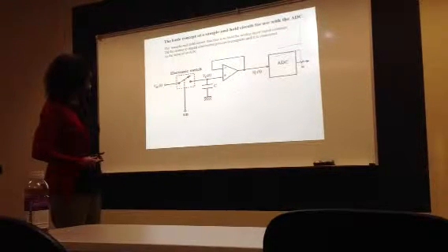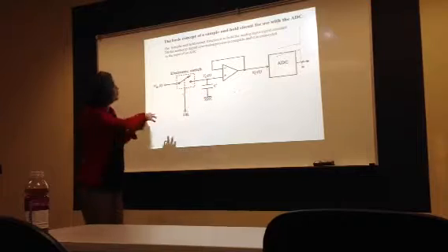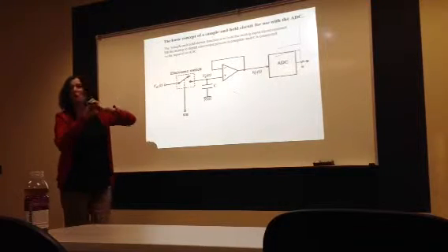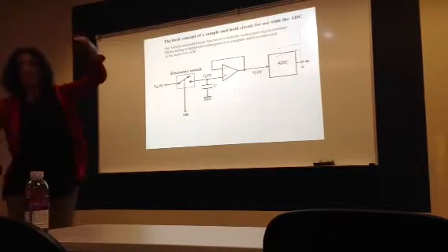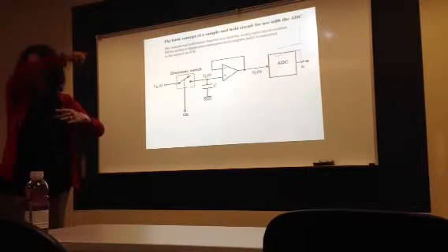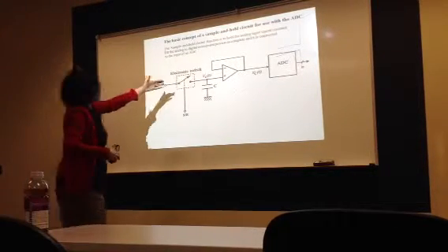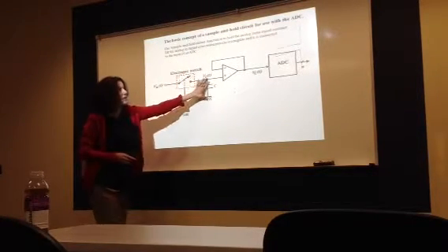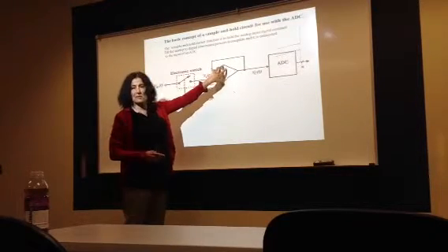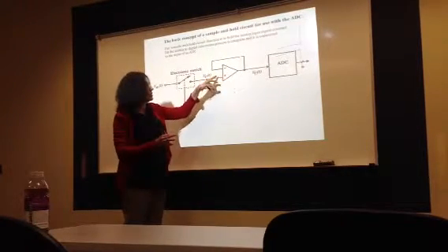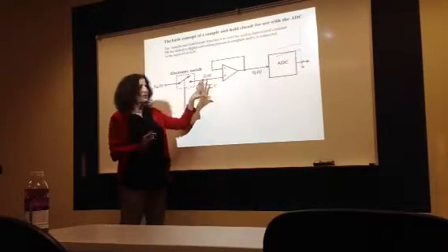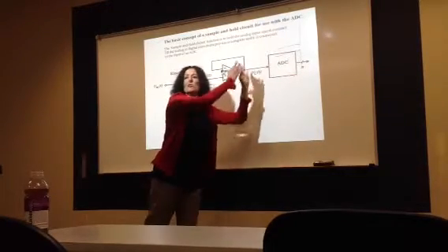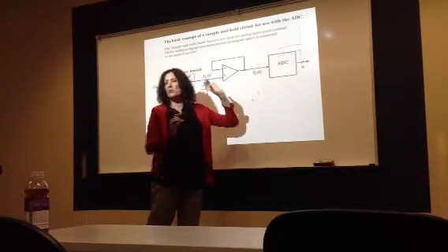What's C? The capacitor. See, the computer samples the signals all the time and then switches to the other one. When you go to the analog input module, it samples that and then switches to the second switch and the circuit completes. As it samples this one, the switch is closed, the sample and hold is charged. So when it opens, it's holding the signal. And it's not going to discharge, because there's isolation, very high input impedance. It's not going to discharge through that. It's holding the signal till the A to D converter takes the analog signal and switches it to the digital count based on the resolution.